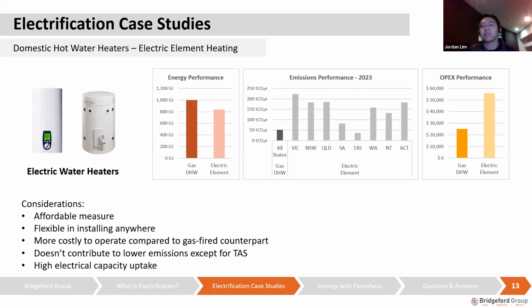So with these reasons, we at Bridgeford Group don't typically recommend electric element heating for domestic hot water unless the site can supply solar PV, because otherwise you would just basically be increasing your emissions performance of the building. Or if you can't install heat pumps at all, because heat pumps do have different kinds of design constraints, we will only then recommend electric element heating as an alternative solution.